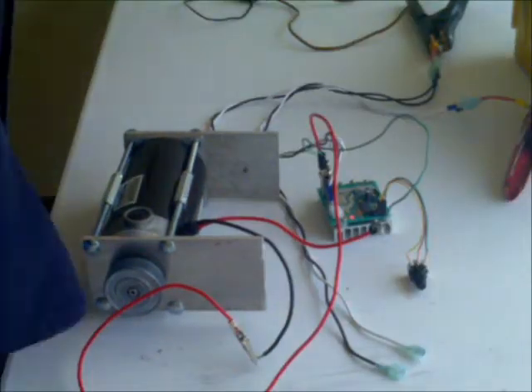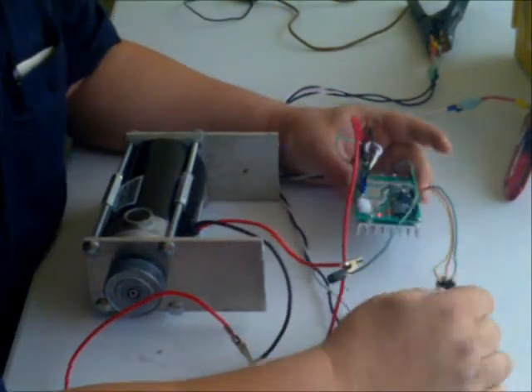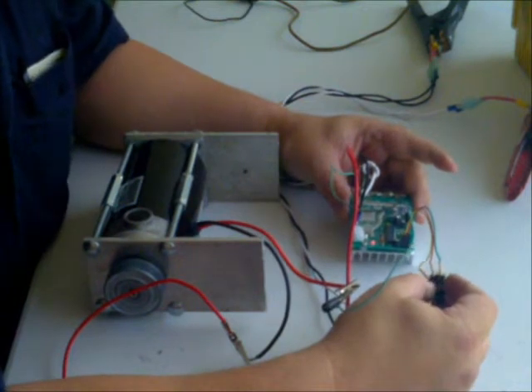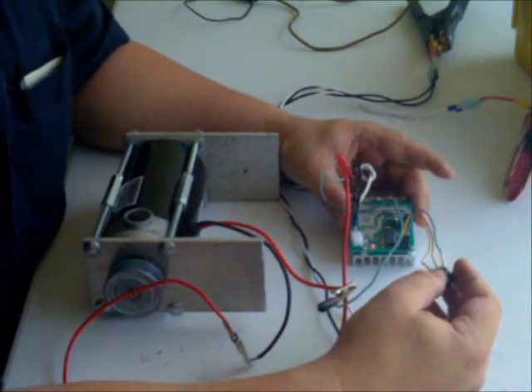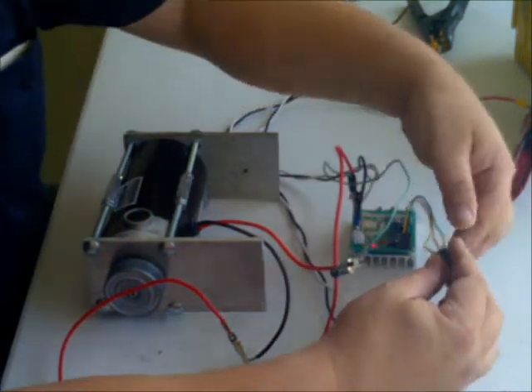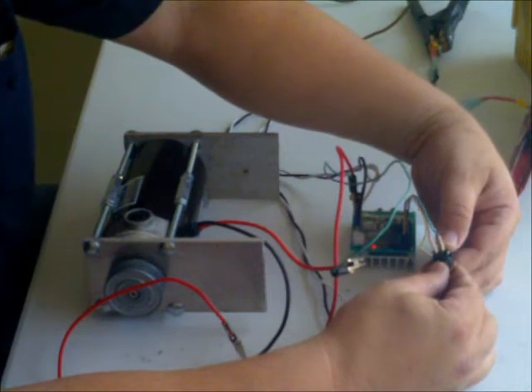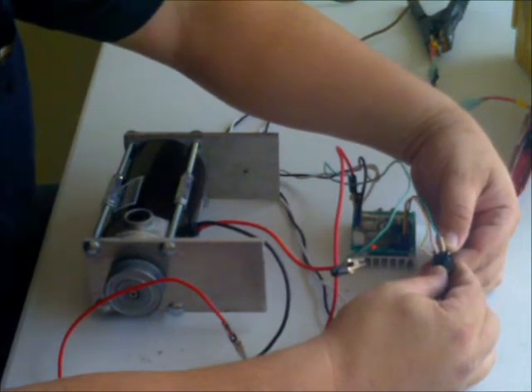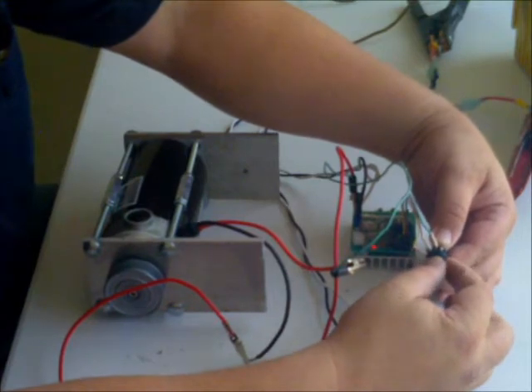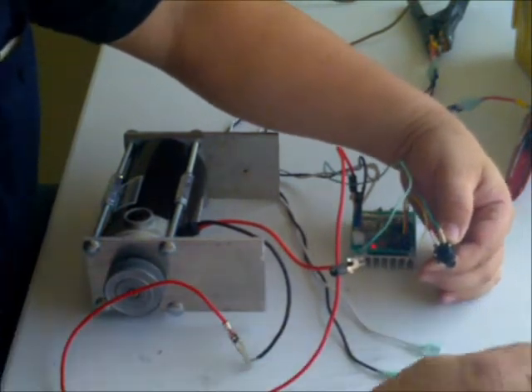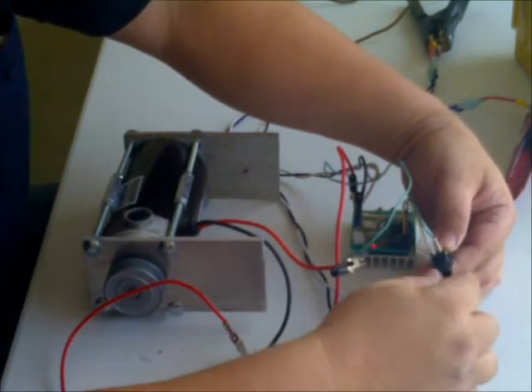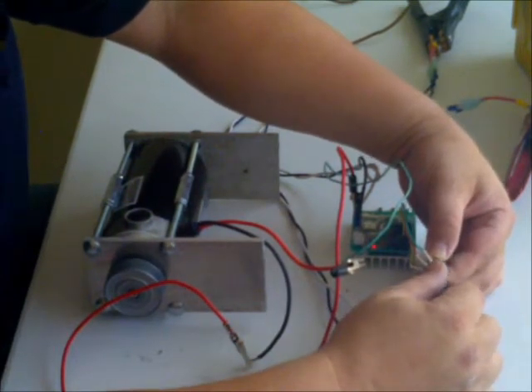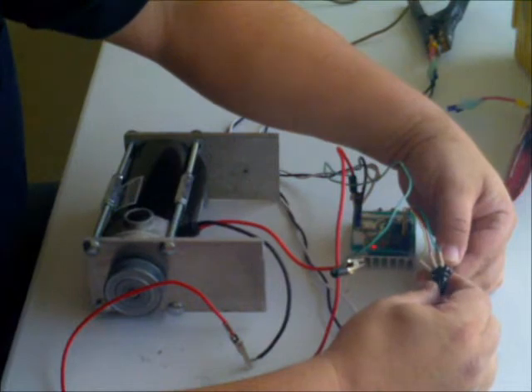All right, I've switched over to this other variable speed unit, basically just a little bit beefier unit. These are available in up to 100-amp service, and some of them even have reversing built-in. Most of them don't, though, in the lower-amp ranges. Just basically turning the potentiometer increases my speed and the motor takes off and it's fully adjustable and variable. This also can be changed. This potentiometer can be changed to a slide-style potentiometer like I had on the other unit here, and that will allow it to work off more of a foot-feed type setup and give you the adjustment and the variability you need to get a full range of speeds out of your power car.